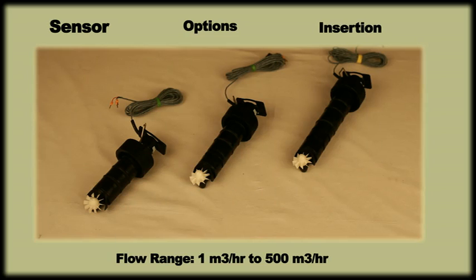Insertion type flow sensors are available for line sizes more than 1.5 inches and can be used for flows ranging from 1 m³ per hour to 500 m³ per hour.